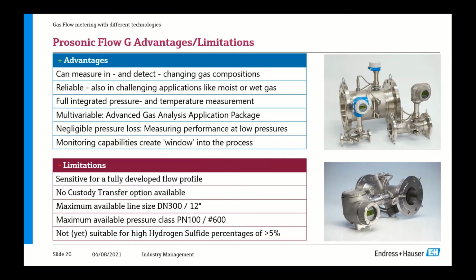Of course, the device has some limitations. The most important one is that it is sensitive to a fully developed flow profile. You need some straight run in front of the flow meter. Unfortunately, we don't have a custody transfer version available. We have a line size limitation of DN300 or 12 inch, and the maximum pressure is class 600 or 100 bar. Not yet available is a material which can measure high hydrogen sulfide percentages of more than 5%.